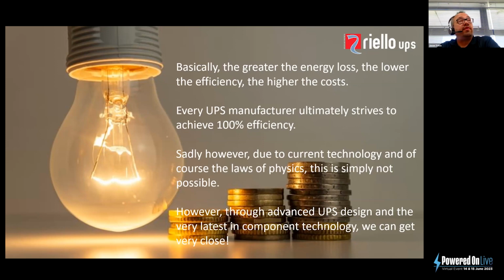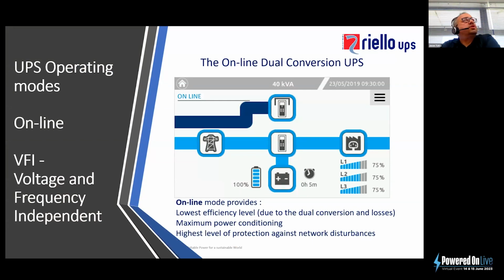Every UPS manufacturer ultimately strives to produce a UPS system that could achieve 100% efficiency. However, sadly, due to current technology and the laws of physics, this is simply not possible at the moment. However, through advanced UPS design and the very latest in component technology, we can get very close. Before we start looking at that technology, I just want to explain a little bit about online dual conversion UPS systems and how they operate, and the 3 typical modes that they will be used in a data center application.